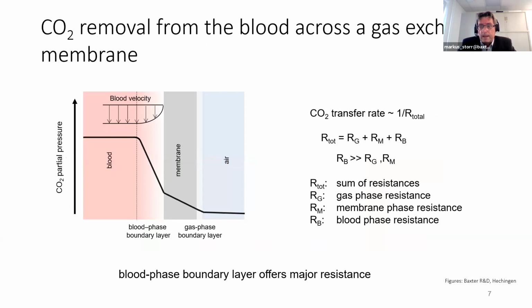So the central process in an extracorporeal CO2 removal device is the transport of carbon dioxide from blood across a gas exchange membrane into the sweep gas by diffusion. The driving force for the gas exchange is the partial CO2 pressure gradient between blood and the gas side of the membrane. The transport is inversely proportional to the resistance. So the transport of CO2 is hindered by three main resistances: the gas phase resistance, the membrane resistance, and the blood phase resistance. And this blood phase resistance, which results from the diffusional boundary layer at the blood membrane interface, represents the by far dominating resistance.